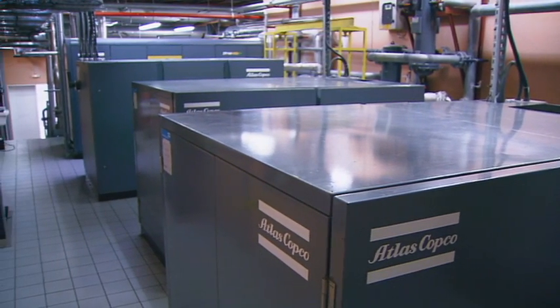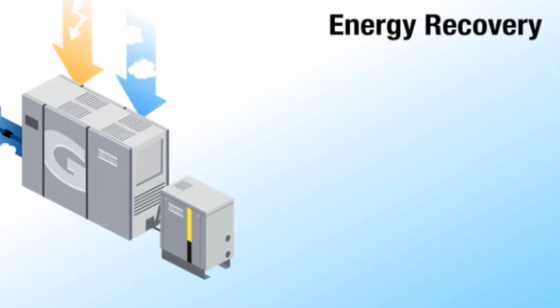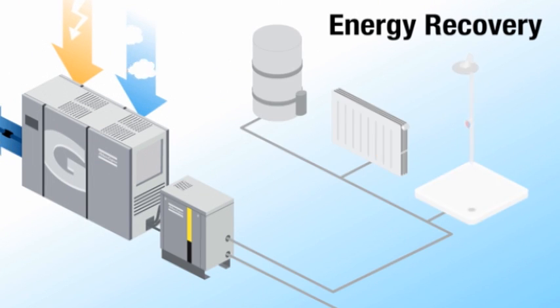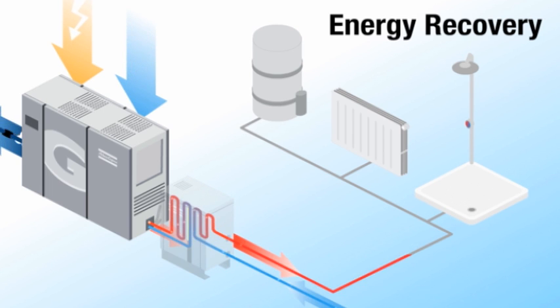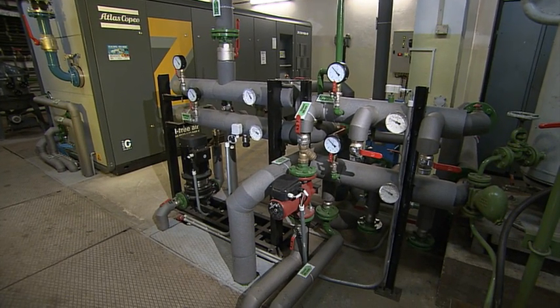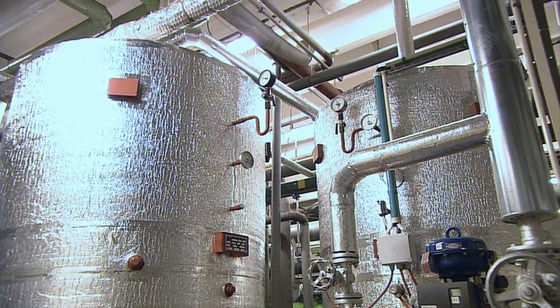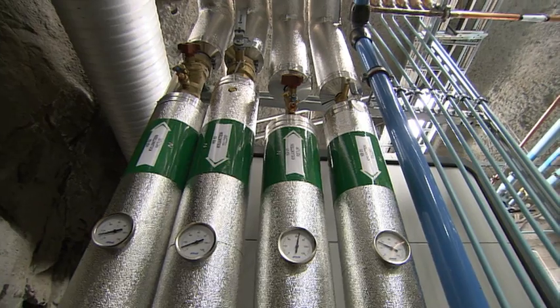Now that the compressed air system has been optimized, we can focus on benefits that the compressed air system can have on other processes. Energy recovery kits convert the waste heat generated by compression to useful heating applications, such as showers or central heating. Processed water or steam is an even better application, as it requires constant heat supply all year round. If your boiler room is close to your compressor room, this will probably be the best investment you will ever make.